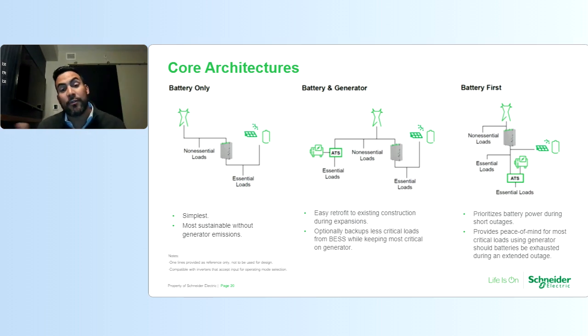And then to the right here, we have a battery first scenario, where your battery energy storage system comes online first before the generator. How this design works is the energy storage system is primarily connected at the main switchboard, and downstream from the main switchboard is an ATS with a generator. So in the event of an outage, SourceBack's automatic interconnection switch will open from the main. It will signal the energy storage system to come online. Inverters come online almost instantaneously, so at the point of outage, say under a second, you can have emergency power. So the ATS will technically, depending on how you have that programmed, remain connected to source one. So before you even can start the generator, your energy storage system will come online first, providing power.